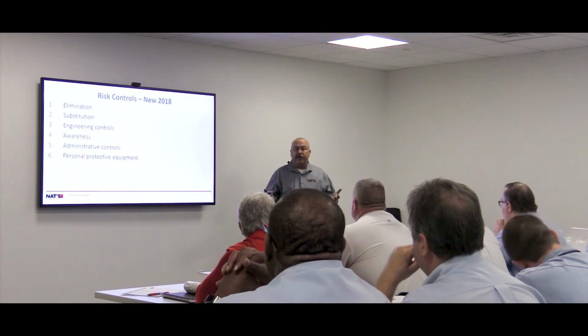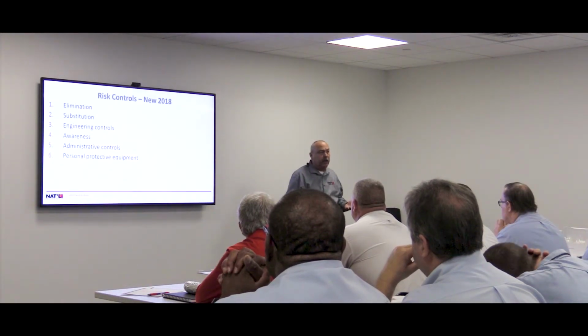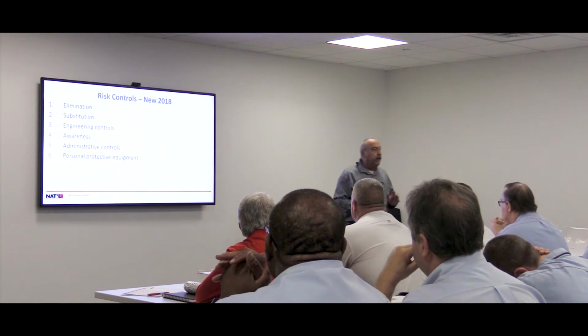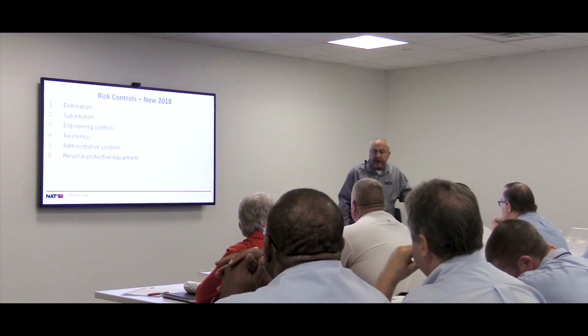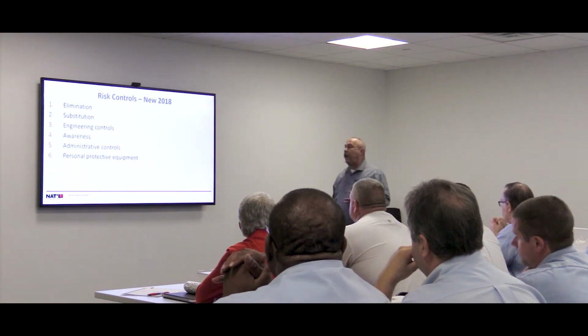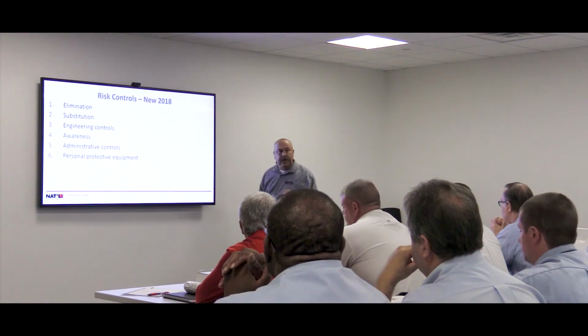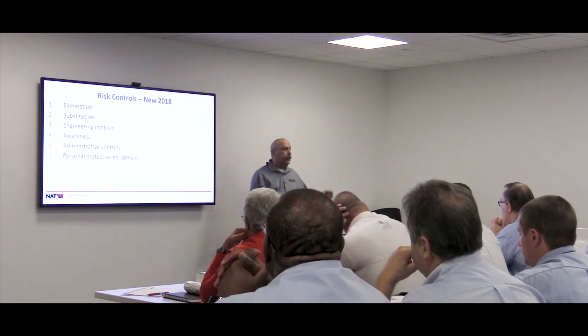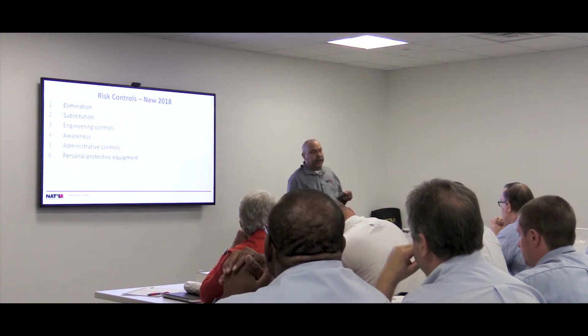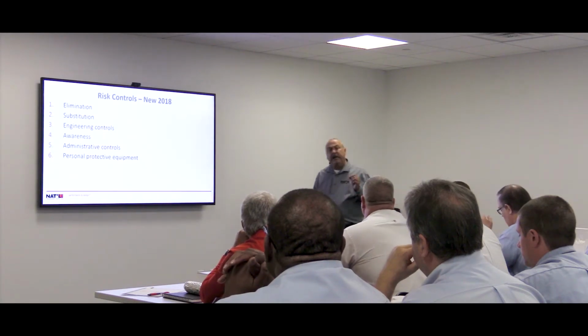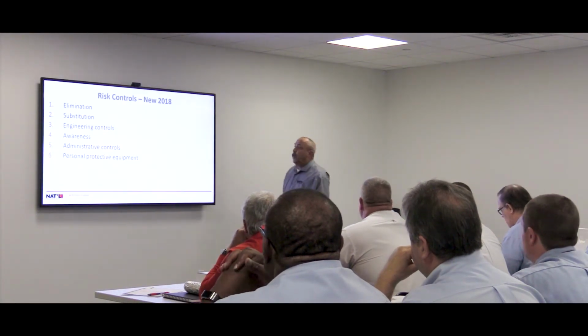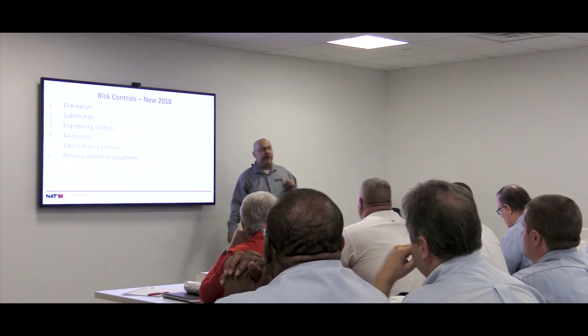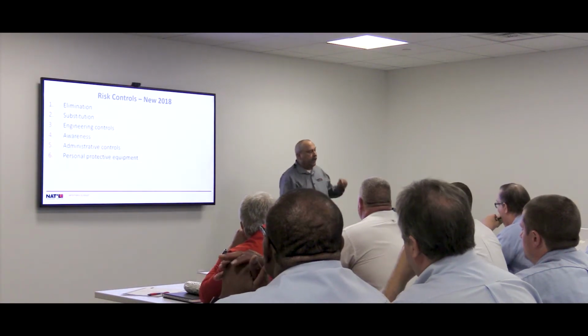Now, there are certain things equipment must be energized to do. You have to have it energized and have load on it to do a proper thermographic survey. There are rare exceptions—some troubleshooting that a control technician or HVAC technician has to do may require it to be energized.